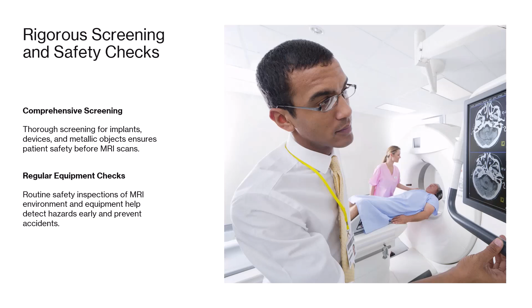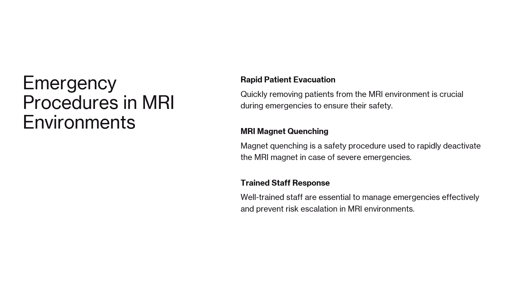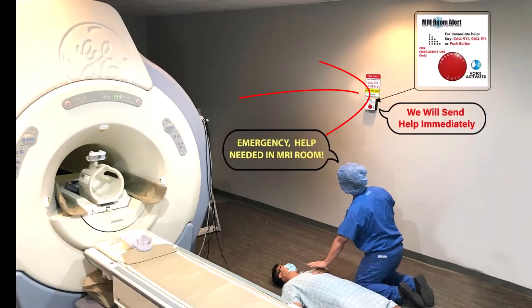Rapid patient evacuation. Quickly removing patients from the MRI environment is crucial during emergencies to ensure their safety, especially when there is a quench. When there is a quench, all of the oxygen is taken out of the room and the patient can asphyxiate. You need a protocol, and you also need proper training and construction of your MRI suite. A simple example is, which way does your patient room door open? If the door does not open pulling outward so that the gases can be released, the gases will push upon the door itself and not allow you to open it if you have to push inward.